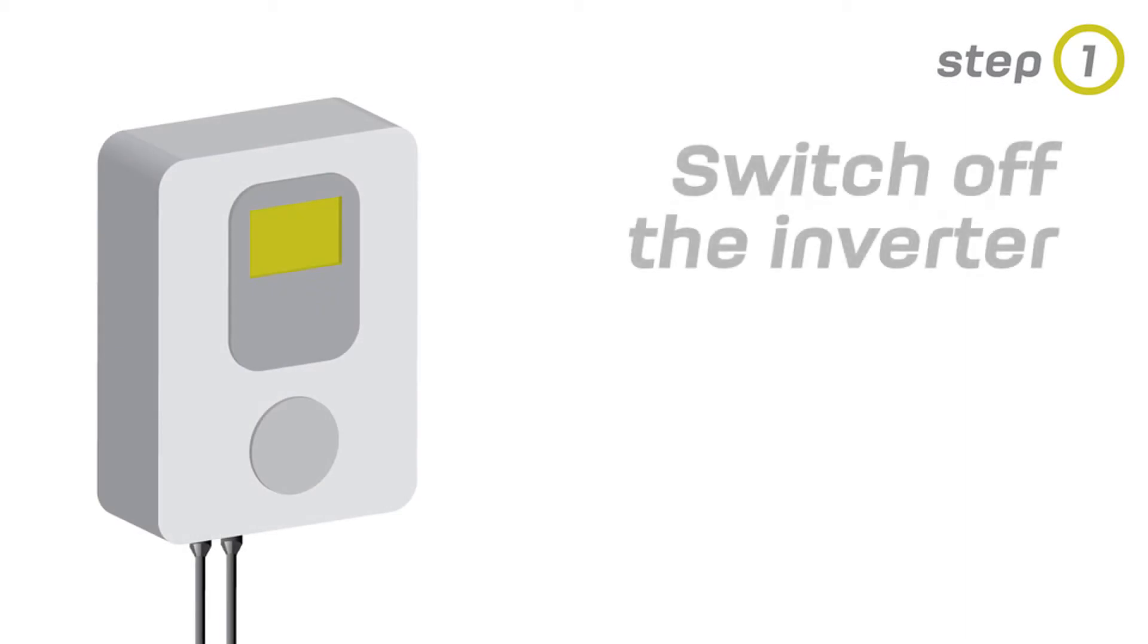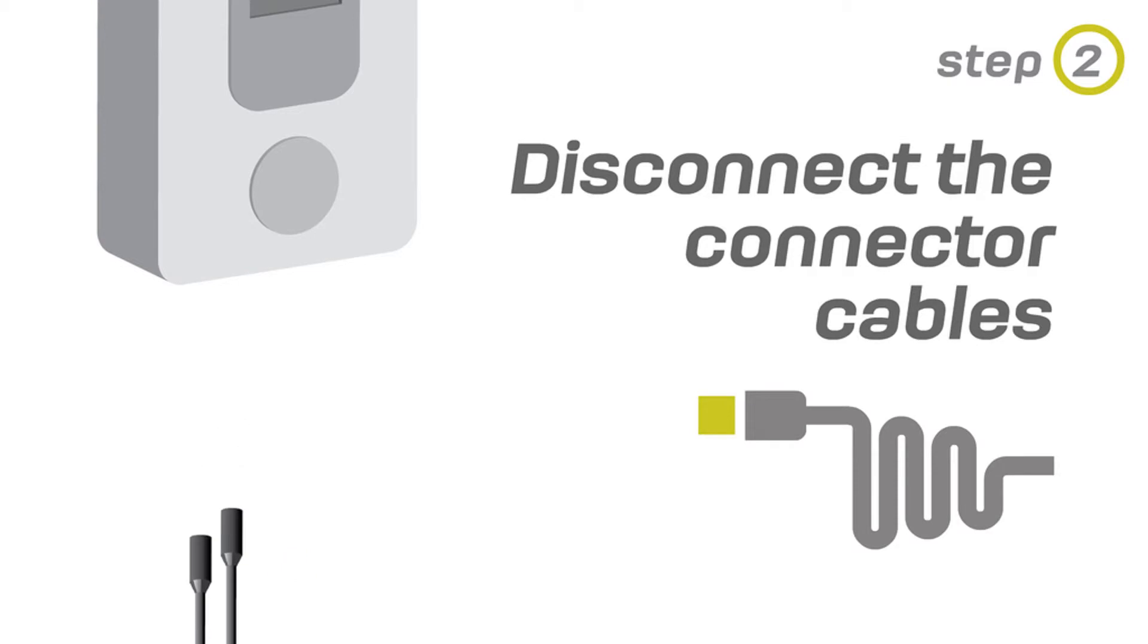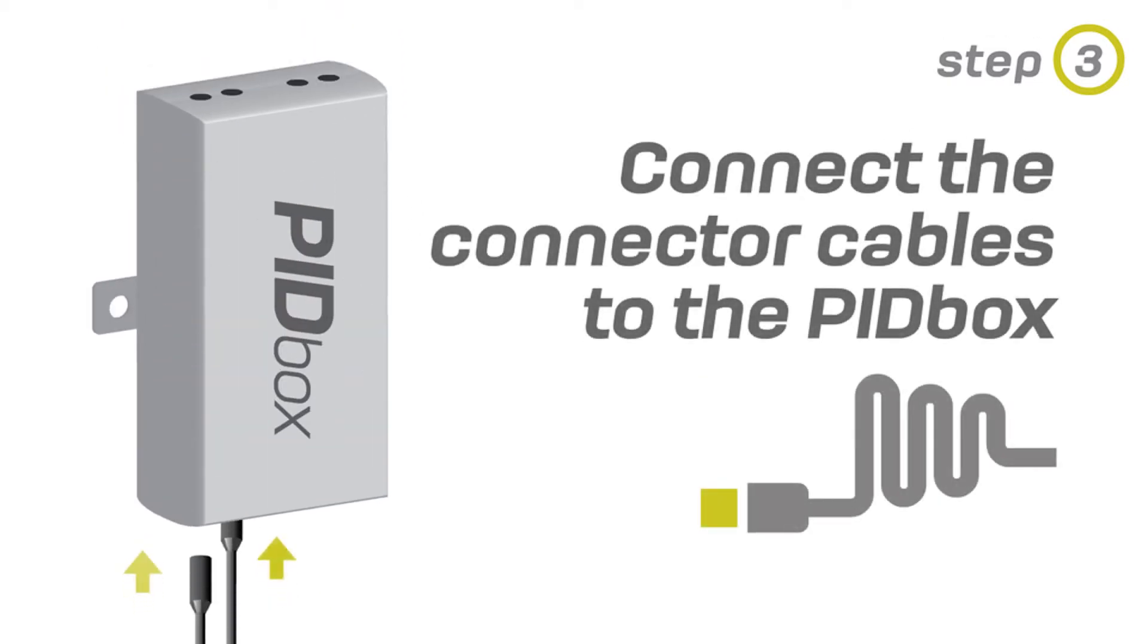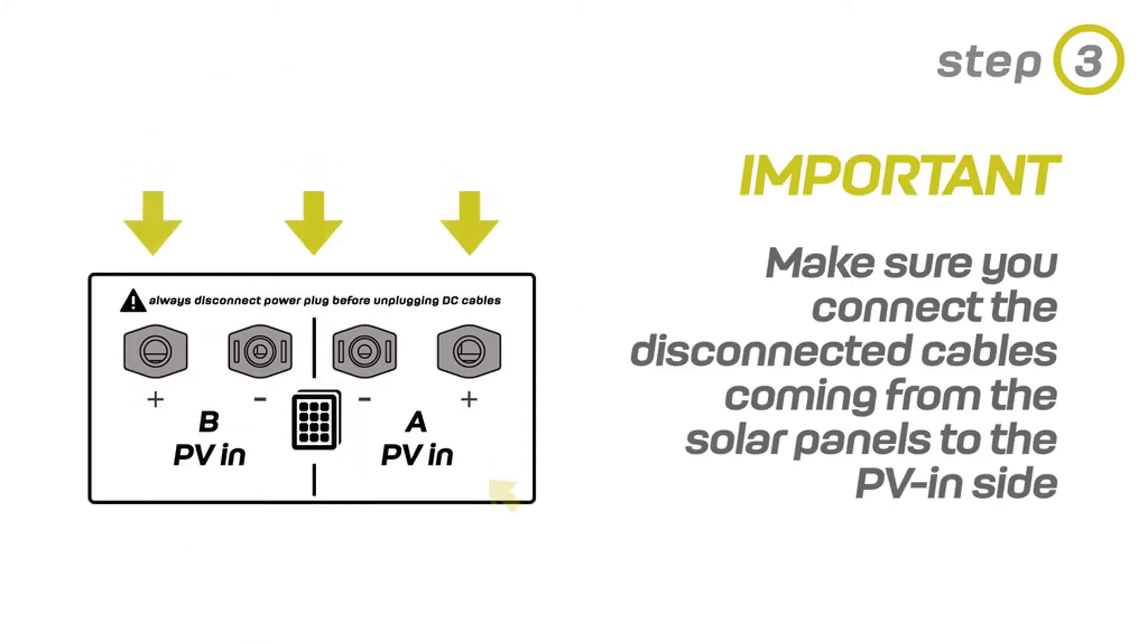Switch off the inverter. Disconnect the connectors from the inverter. Connect the connectors to the PID Box Mini. Make sure you connect the disconnected cables coming from the solar panels to the PV-in side of the PID Box Mini.